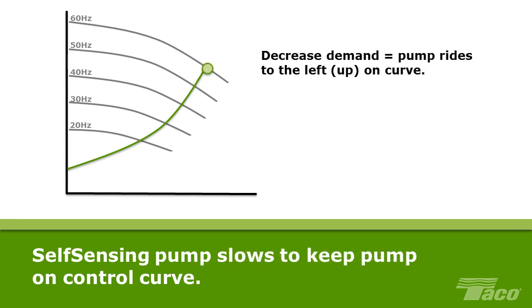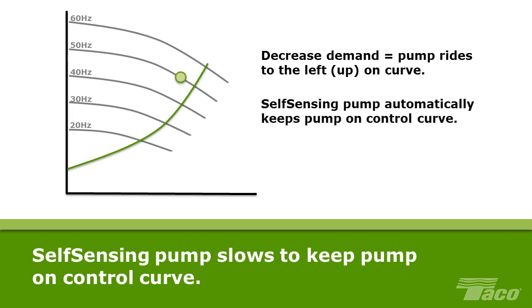A similar thing happens in reverse when there is less demand in the system. As flow decreases, pump head increases and the operating point rides to the left and up along the pump speed curve. The self-sensing pump automatically responds, slowing to keep the pump on the control curve, which keeps the pump operating at the most efficient point for system conditions at that time.